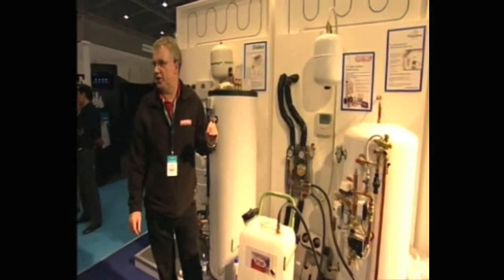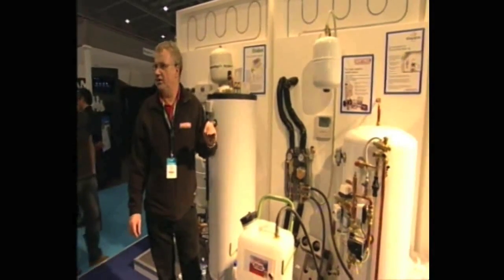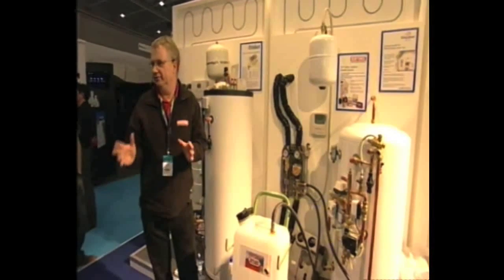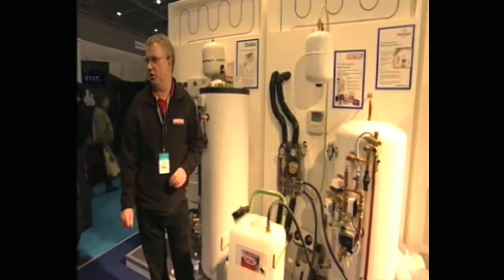We need to get the system pressure about one bar above the pressure of the height of the top of the manifold. So typically, that's going to be the system pressure to about one and a half bars.